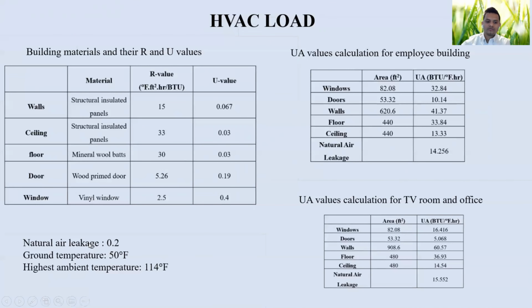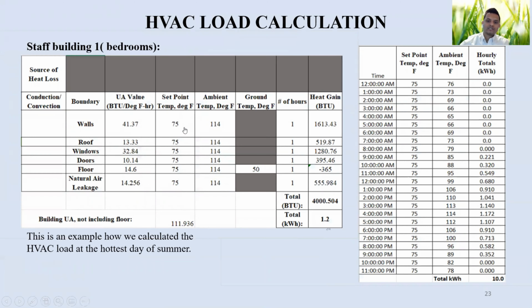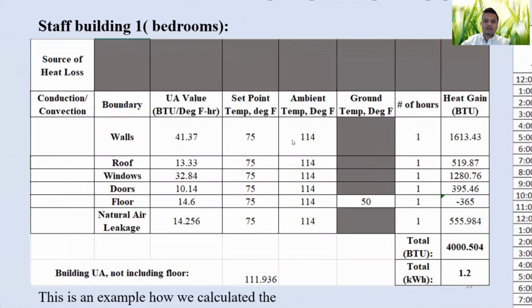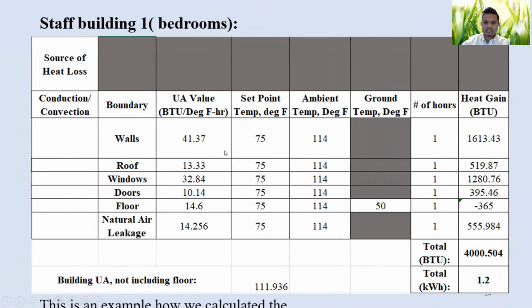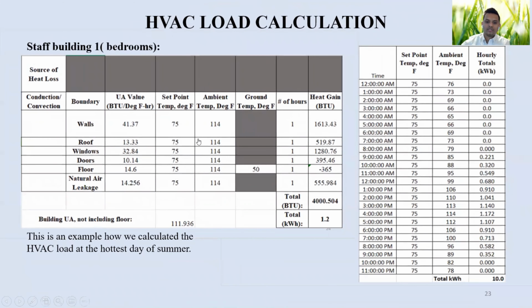For the calculation, we use the natural air leakage at the standard ratio of 0.2, and the ground temperature was 50 degrees Fahrenheit, and the highest ambient temperature is 114 degrees Fahrenheit. So to calculate the HVAC load, we assume 114 degrees as the highest temperature in a single day. In this way, we calculated how much energy is needed to cool down the building to 75 degrees. That comes to 4,000 BTU of energy that needs to be extracted from the building, which is equivalent to 1.2 kilowatt hour in 1 hour to keep the building at 75 degrees at the hottest time of 114 degrees Fahrenheit.